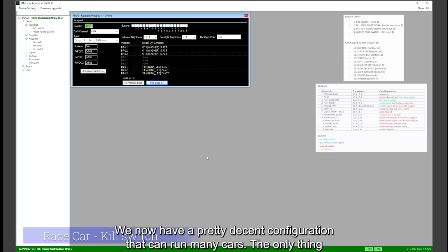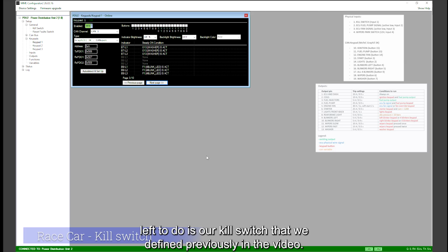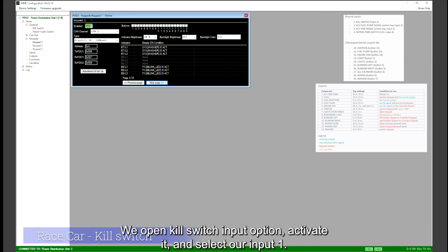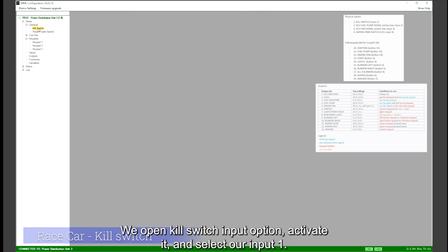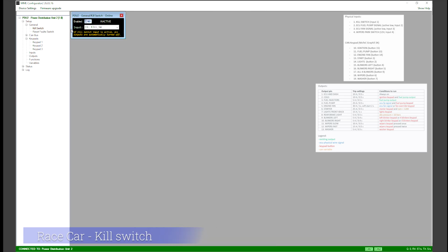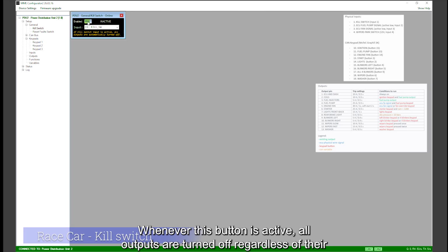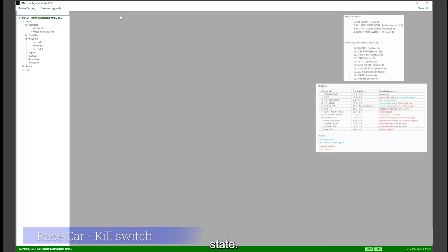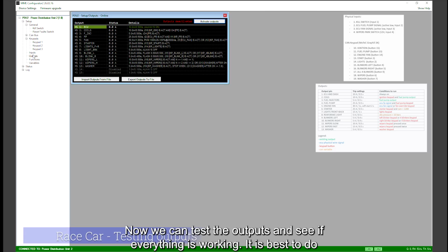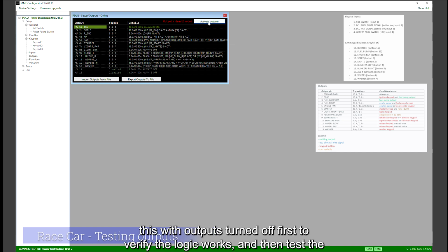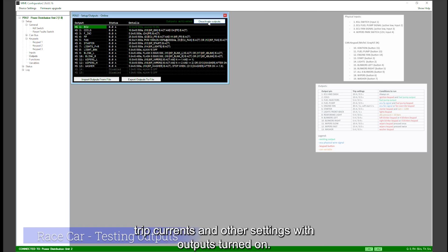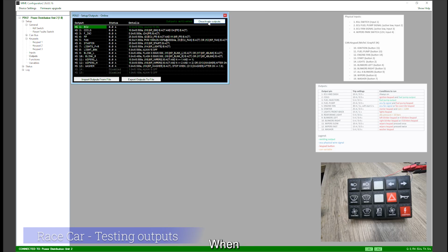We now have a pretty decent configuration that can run many cars. The only thing left to do is our kill switch that we defined previously in the video. We open the Kill Switch Input option, activate it, and select our input 1. Whenever this button is active, all outputs are turned off, regardless of their state. Now we can test the outputs and see if everything is working. It is best to do this with outputs turned off first to verify the logic works, and then test the trip currents and other settings with outputs turned on.